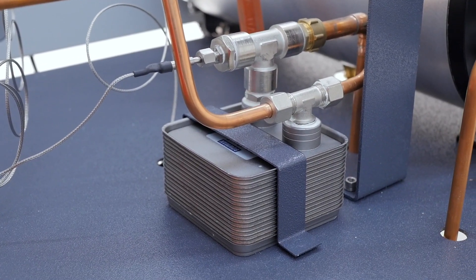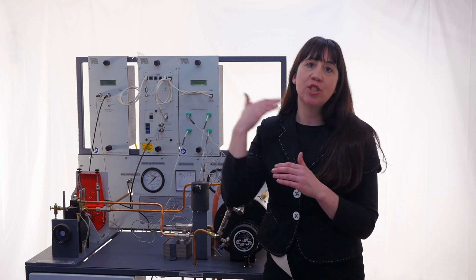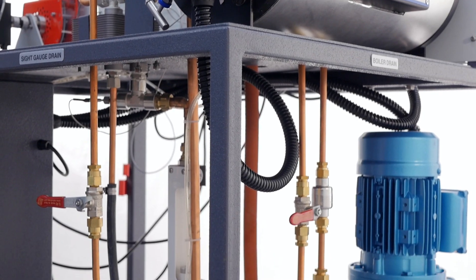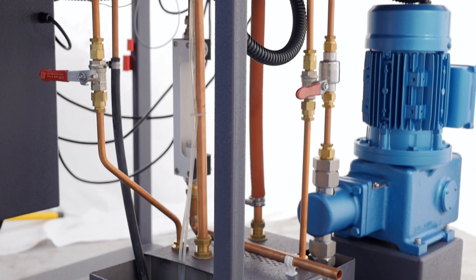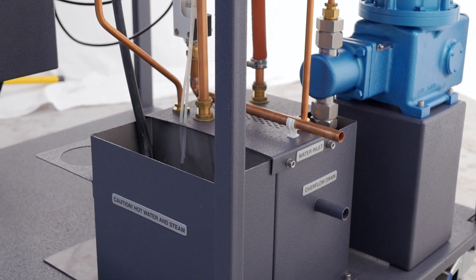The exhaust steam from the engine passes through a condenser which is the heat exchanger. Cooling water circulates through the heat exchanger cooling the exhaust steam. The steam condenses and drains out of the connection below the condenser to the condensate collector or to the waste tank next to it.